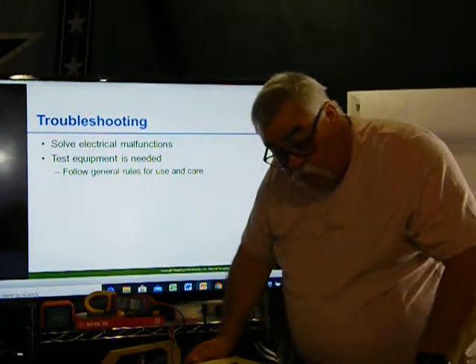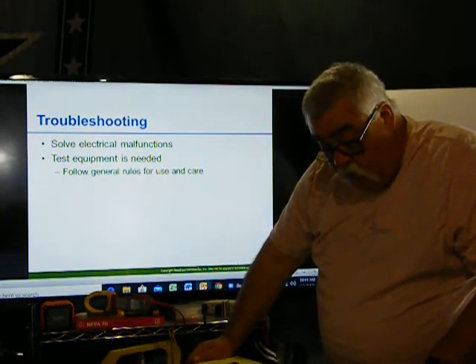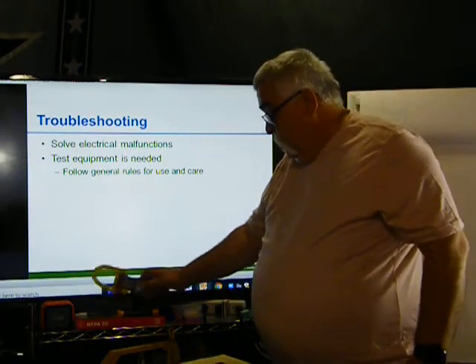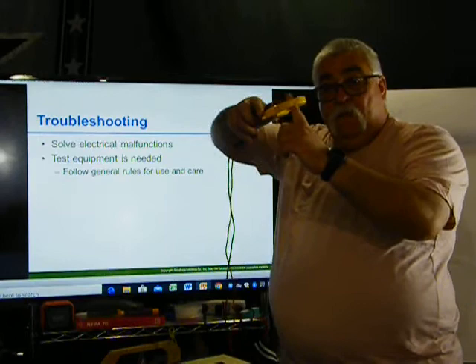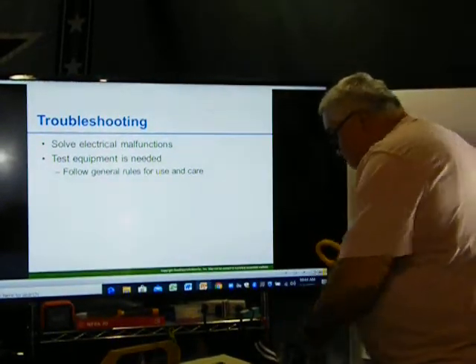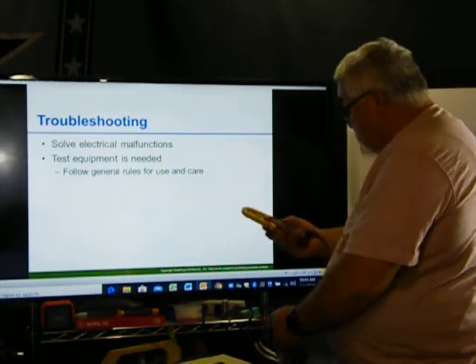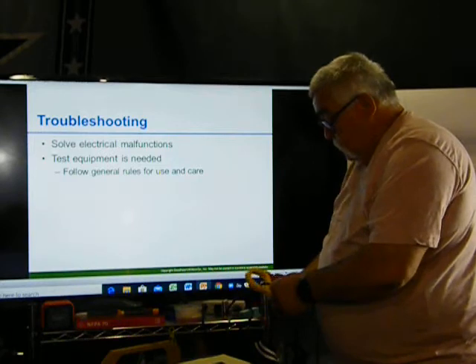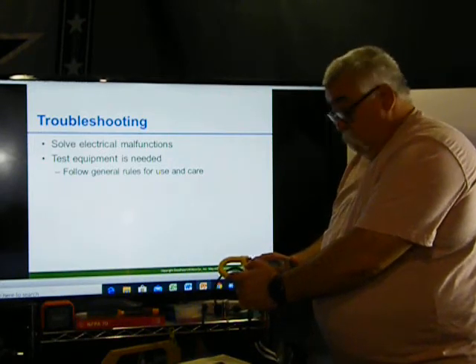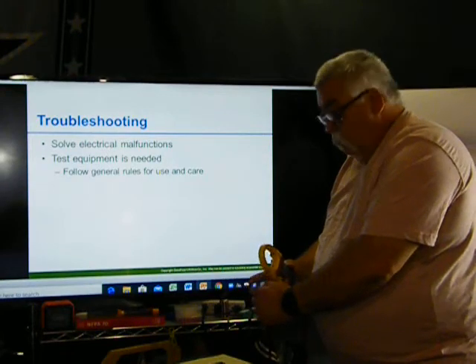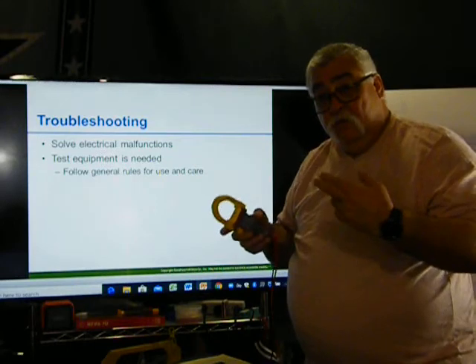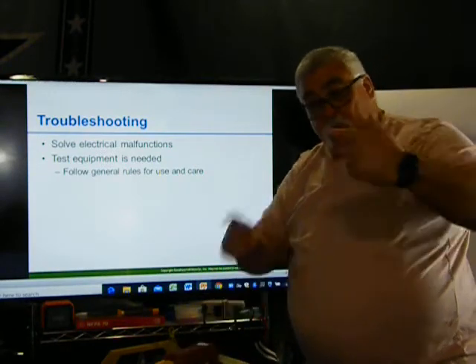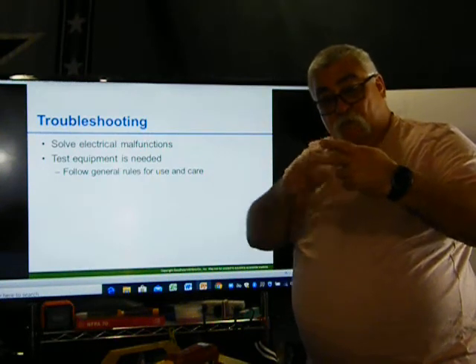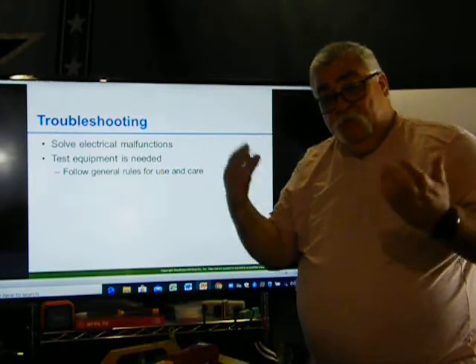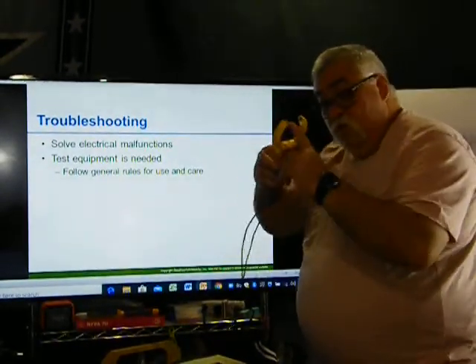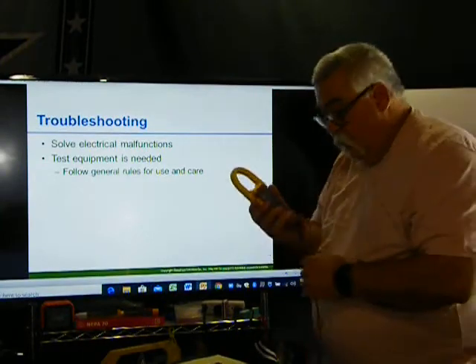Make sure clamp-on instrument jaws are completely closed and on one conductor at a time. Okay, so when you're testing, one wire. It's like if you get this and you put it around the cord, and it's got something plugged in, if you put it on the amperage, it gives me nothing. Well, what it's doing is it's reading that hot and neutral. That hot and the grounded wire. Well, what happens if I got 5 amps here and I got 5 amps here? Well, what's 5 amps going to do to the 5 amps here? It's going to make it 0, so it's going to give you no amperage. So you only want to do one wire at a time. Never try to get around a cord and check that way.